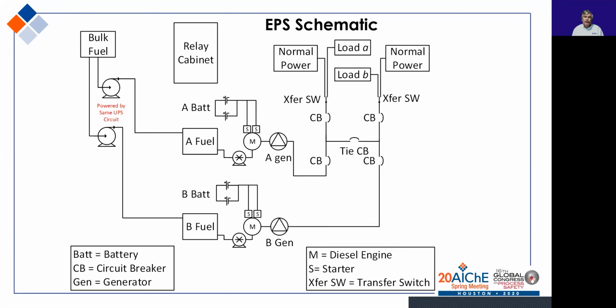And if normal power is not available, the transfer switch puts generator A output into load A. That's part of the load. Generator B likewise has a transfer switch. If normal power is not available, it puts its output into load B. Both generators can handle the total load A plus B, and for that to operate, the tiebreaker circuit breaker must close so that one generator can feed both loads.